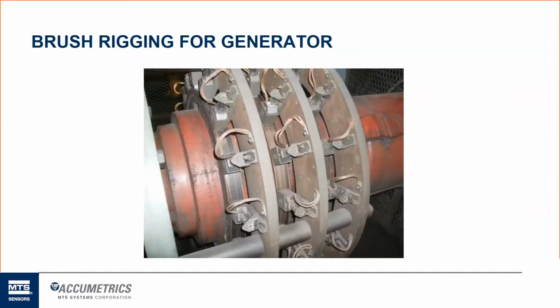So in a brushed system, which is what this picture is, all of your brush rigging and your circuitry is out in the stationary world. They bring that across with this brush rigging assembly. They bring DC power source across to that, and they contact these slip rings that are press fit onto the shaft itself. So that's how they're getting their DC power source out to the rotating shaft as the machine is spinning around.